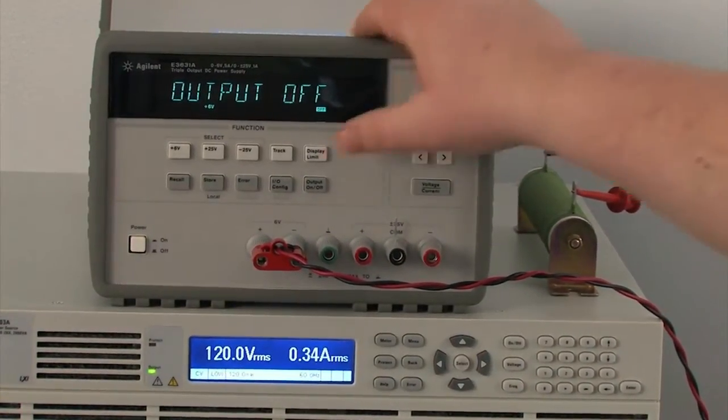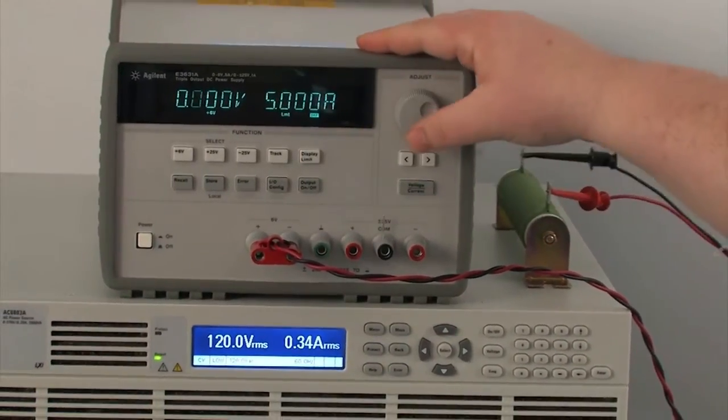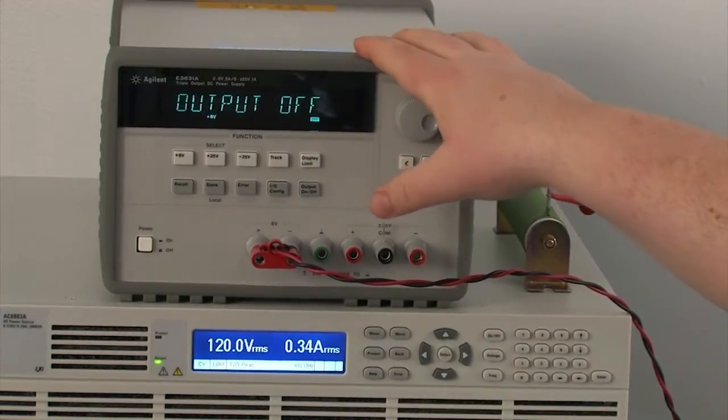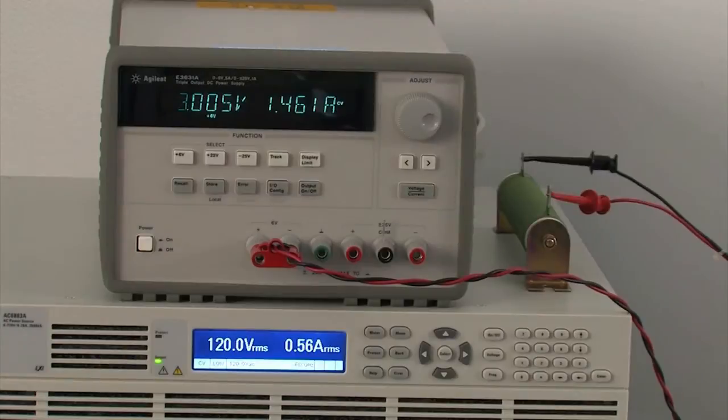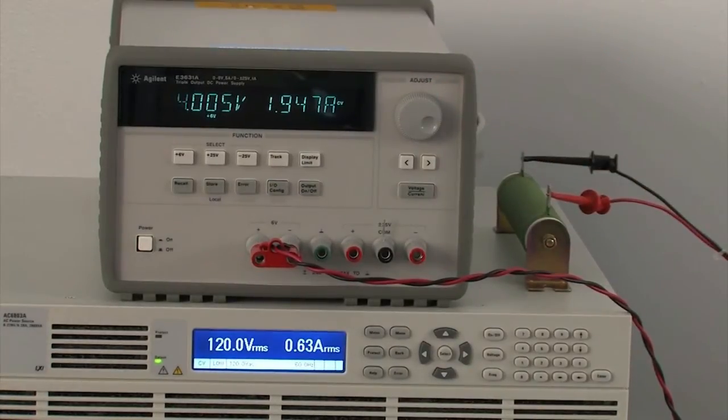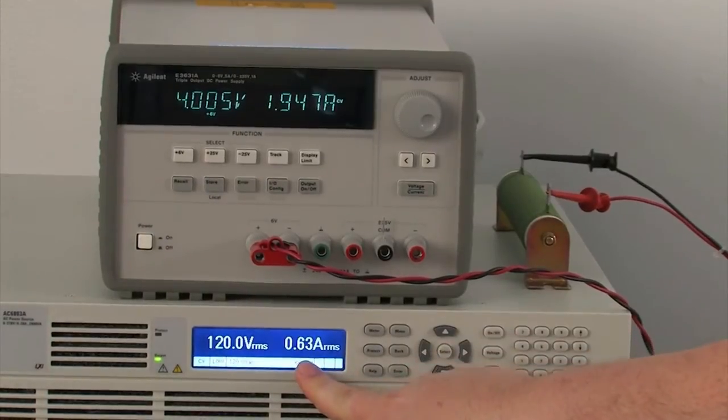So what we're going to do here first is to show you that this is really working. We're going to just set this to 4 volts and I have a 2 ohm load on there. So when I turn it on, it's going to draw around 2 amps. You can see that the current draw went up to 0.63 amps RMS.